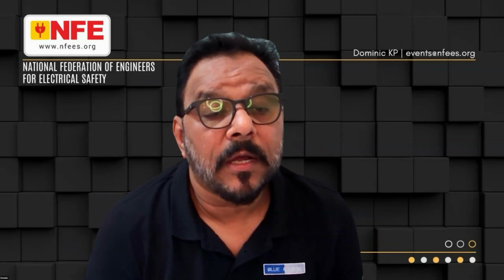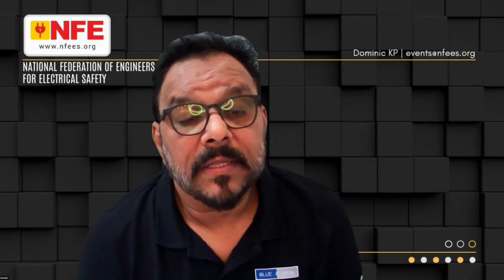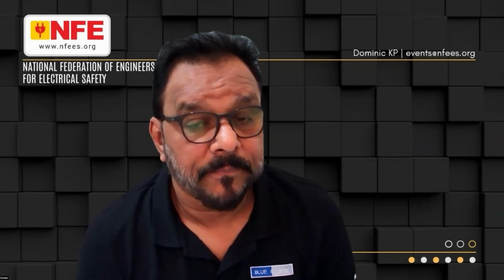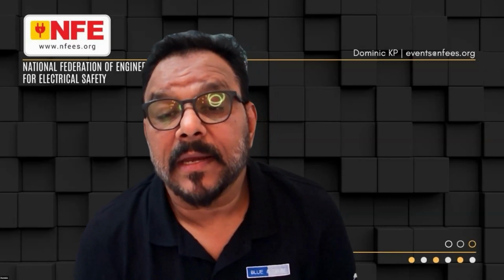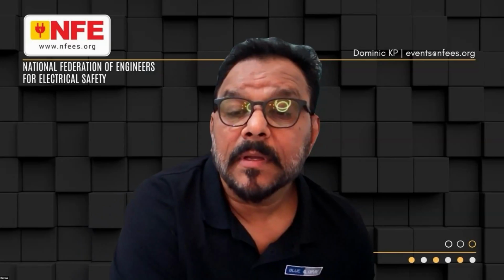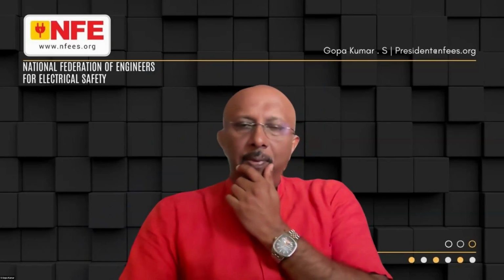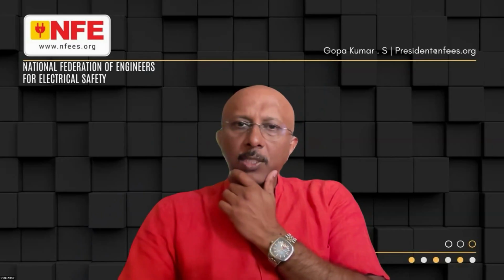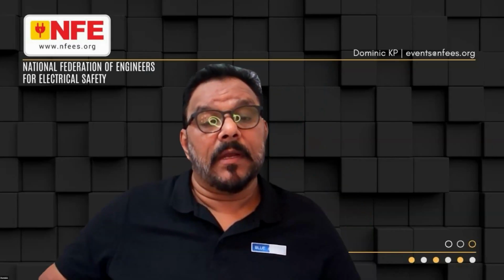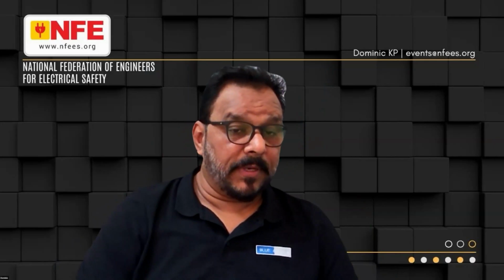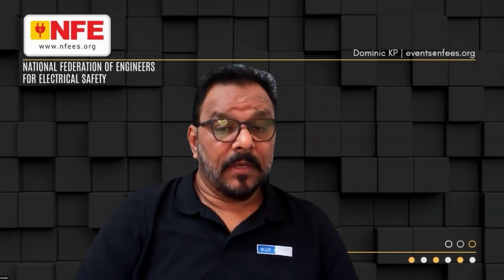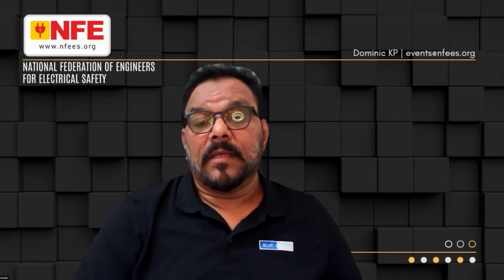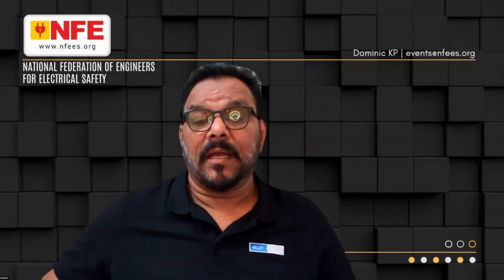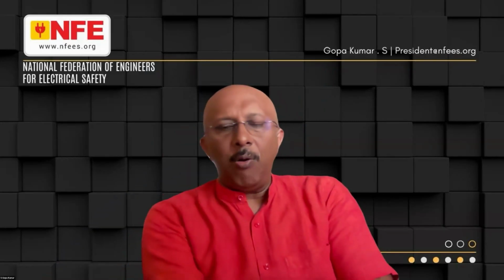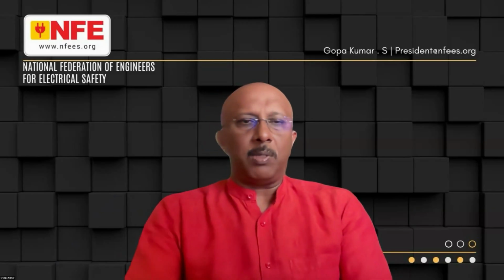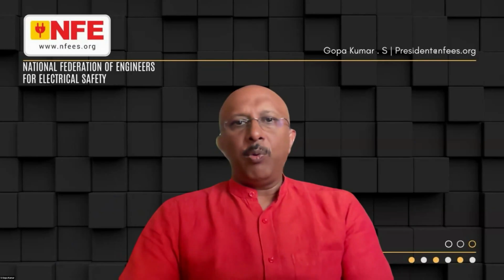We have installed a Cummins make 250 kVA DG set in our 132 kV substation for auxiliary supply. What is the stack monitoring guideline? I'm not clear. Is it to be more building? I don't know, the question is not very clear. However, our subject is not about the substation. Our subject is specific to the hospital. So no hospital will have a 132 kV substation.